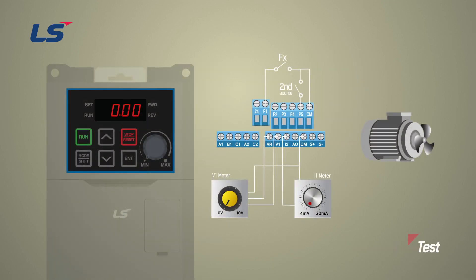Let's test it. Set the multifunction input terminal P5 as the second source and set the command source as the terminal block. The frequency reference source of the original operation will be set as 0 to 10 volts and the frequency command of the second operation will be set to 4 to 20 milliampere. Adjust the voltage source to 2.5 for 14 hertz and set the current source to 12 milliampere.